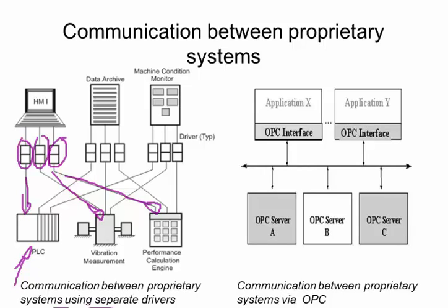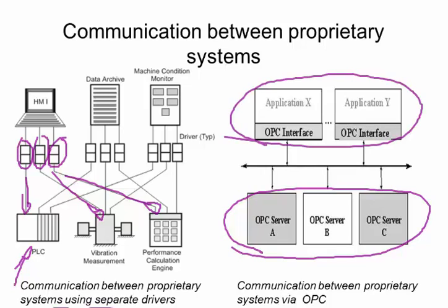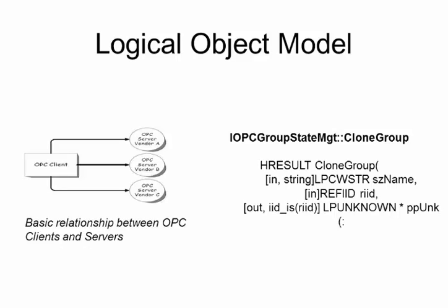The intent of going to OPC was that each of these three devices on the bottom would have an OPC server on it, and then all the devices up on the top would have an interface that could just talk to any of these devices as long as they implemented the OPC server in a standards compliant manner. So the intent was, instead of having lots and lots of proprietary drivers, there would be one way to pull data up from the floor. So that's where it's come from.